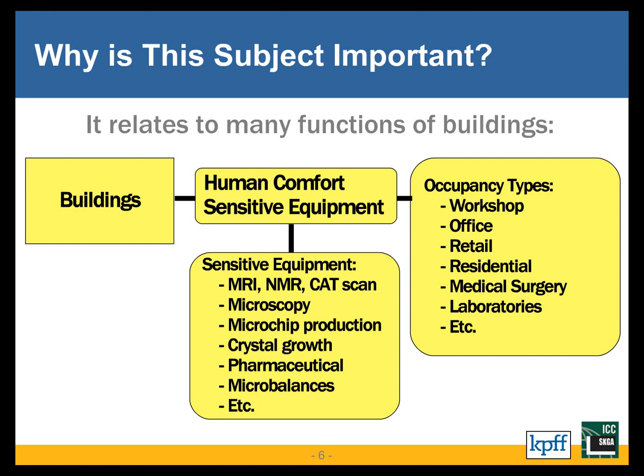With regard to equipment, we cross over into a range of very small vibrations that are generally not feelable or sensed by humans. Those would include imaging equipment like MRI, nuclear magnetic resonance, or CAT scan machines, microscopy — particularly photographic microscopy — microchip production such as growing crystals for microchips, pharmaceutical processes, microbalances, and a whole host of other sensitive equipment.